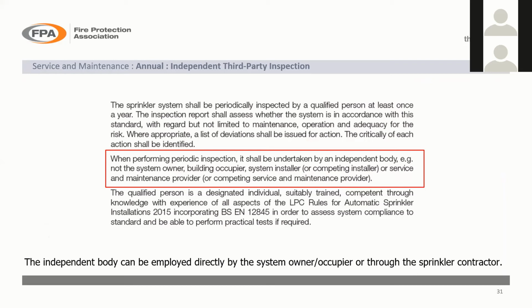The inspection report shall assess whether the sprinkler system is in accordance with this standard with regard to, but not limited to, the maintenance, operation and adequacy for the risk. So where appropriate, a list of deviations shall be issued for action. So the criticality of each action shall be identified. And the way we do that is we provide a report, and if something's really critical, we identify it as red. If it needs action, well, it's not going to result in a system failure, so to speak, we sort of flag it up as an amber.